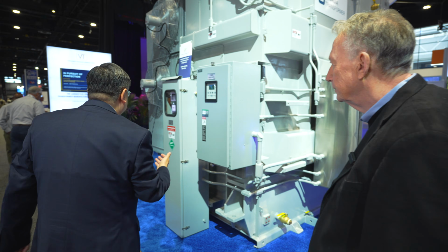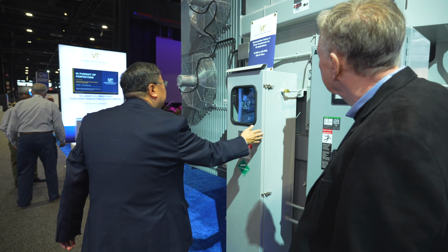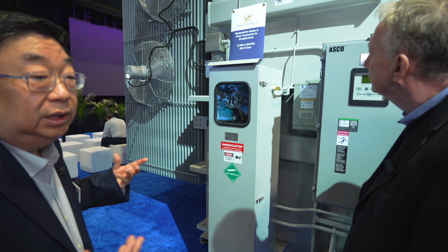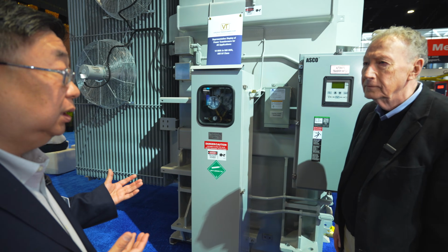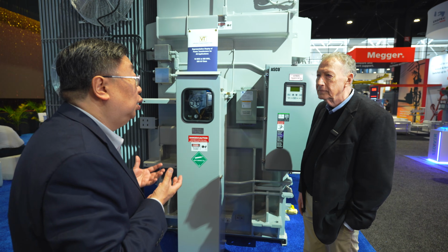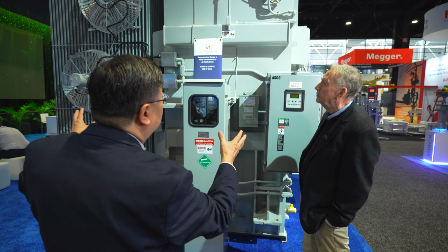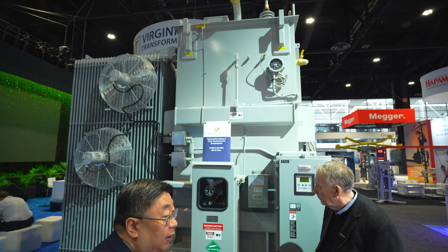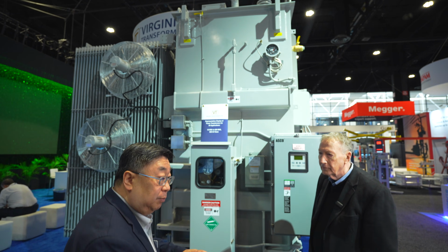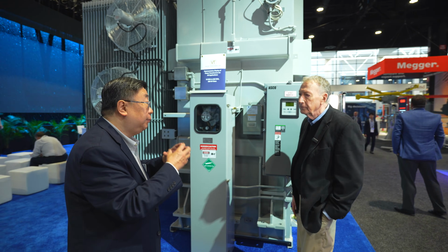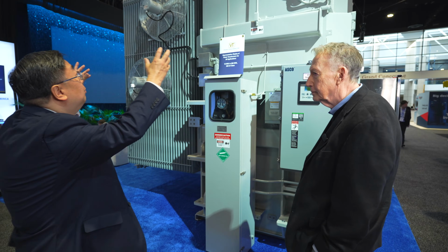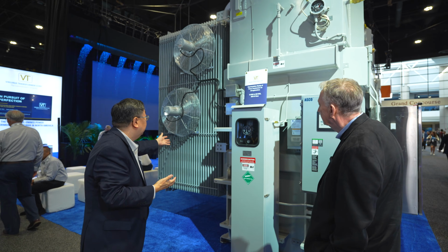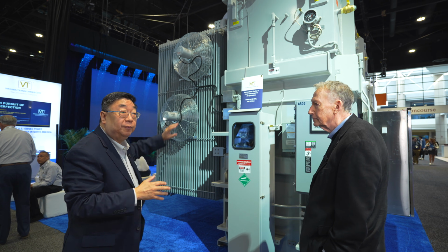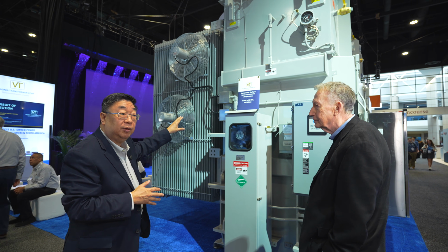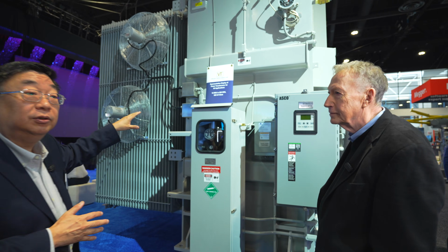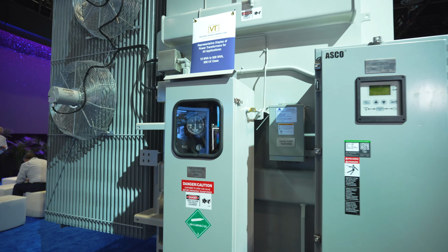Then there's this unique box you see here. In a lot of cases these transformers are so big that it's not possible for us to ship them fully assembled like this. During what's called the factory acceptance test, we simulate and test it under the exact same conditions as in the field—we assemble all the bushings, radiators, and other accessories, and fill it with oil, anywhere from 5,000 to 10,000 gallons, and then we test it.